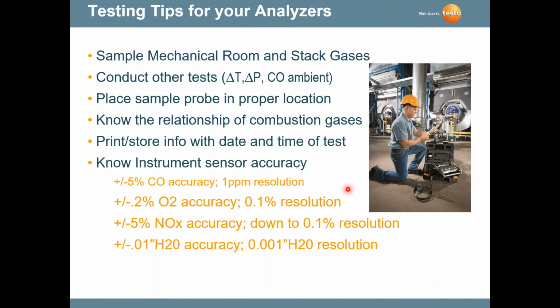Here are some tips. Mechanical room and stack gases, sample both. You can do a lot of things, not only combustion efficiency, but delta T. Know your probe location. Know the relationship of those gases. Have an instrument that prints and stores the data, because you want to be able to pull that up at a later date. Instruments are designed to run very accurate sensors.